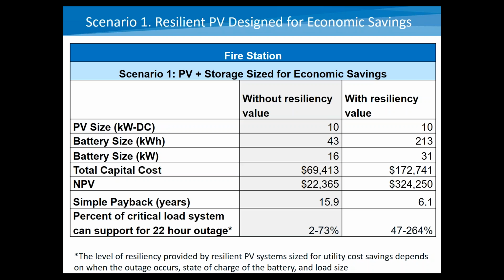And then the percent of the critical load that the system can support for a 22-hour outage varies between 2 and 73%. The reason there's such a wide variation is because the level of resiliency provided by that system really depends on a few things. It depends on when the outage occurs, because the solar resource and the size of the load vary by time of day and time of year. And then the state of charge of the battery varies as well. So if this site had just been using the battery for peak shaving, then the battery state of charge might be low, and so it might provide less resiliency than a fully charged battery.